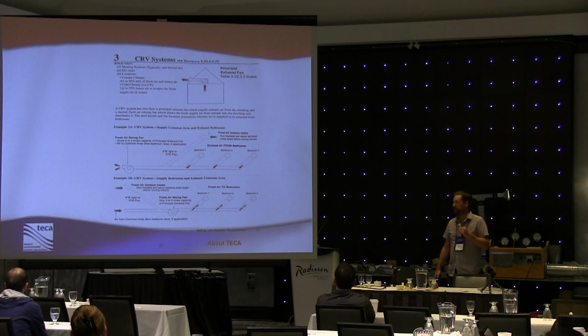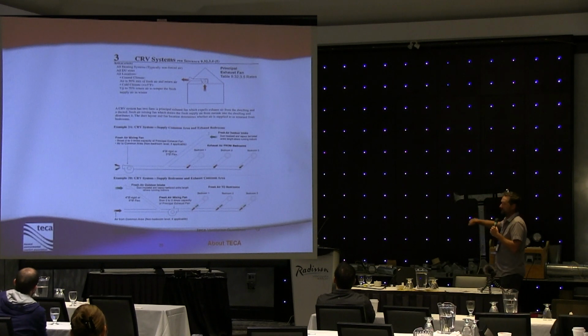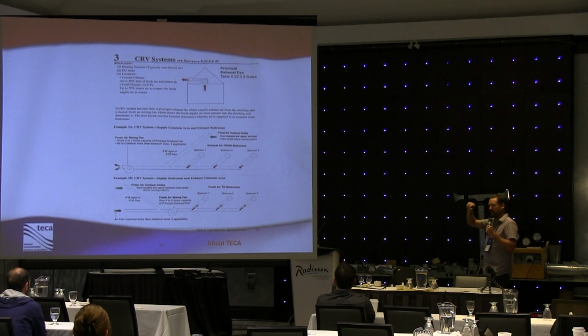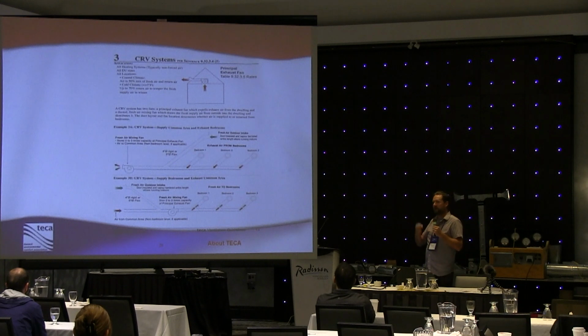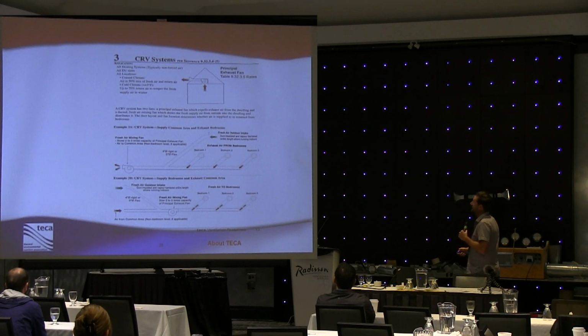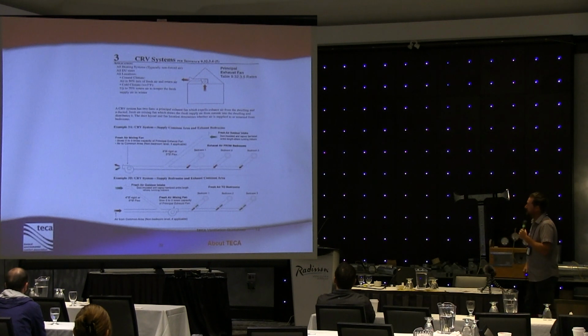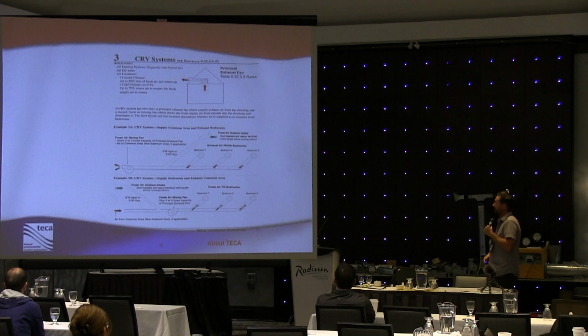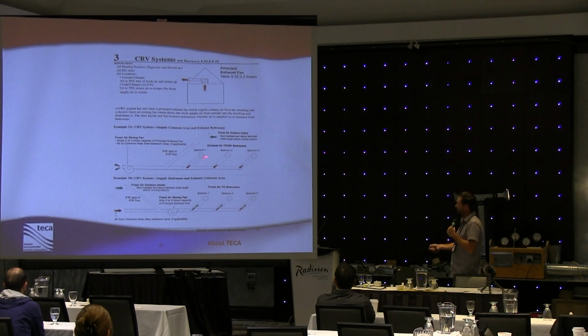However, if you do dig into the BC Building Code, it says that we're to provide fresh air to every bedroom. Well, in a roundabout way, this system will provide fresh air to the bedrooms. Hopefully the doors are undercut enough to allow that air flow to return to those bedrooms and to get some fresh air in there. However, I can see this system in the future possibly being less likely to make it back into a building code, only because we're not directly delivering fresh air to bedrooms.